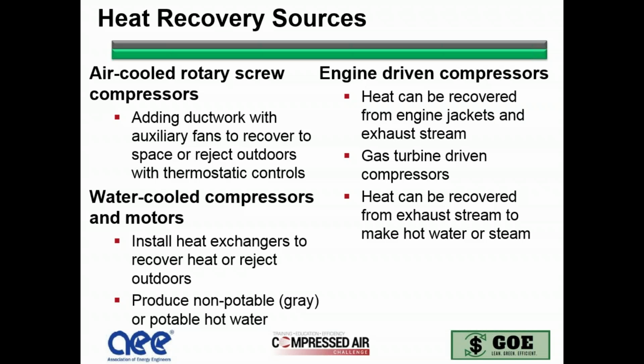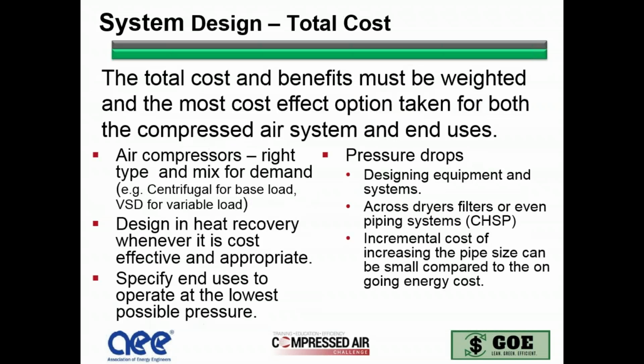Water-cooled compressors and motors, you can install heat exchangers to go through and recover the heat or reject it outside. This can be used not only for heating, but it can also be used to produce non-potable gray water or potable water used for domestic hot water. There are cautions you have to take with the type of exchangers you use. And then of course, engine-driven compressors can also be recovered from the heat of the engine jackets and the exhaust stream. Gas turbine-driven air compressors can also allow the same thing. The heat can be recovered from them, from the exhaust stream, to make hot water or steam as well. So again, these give you the opportunity for even additional energy savings through heat recovery.